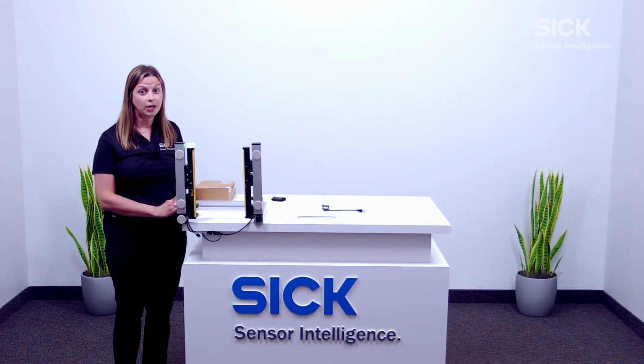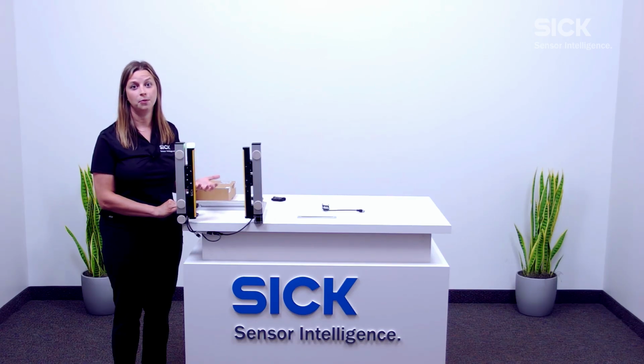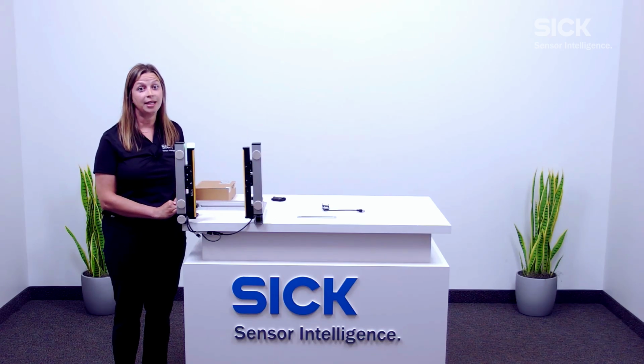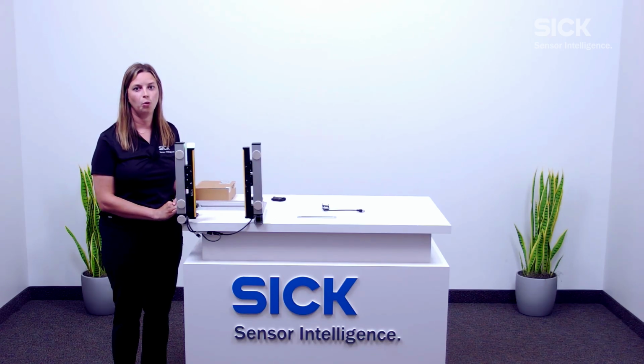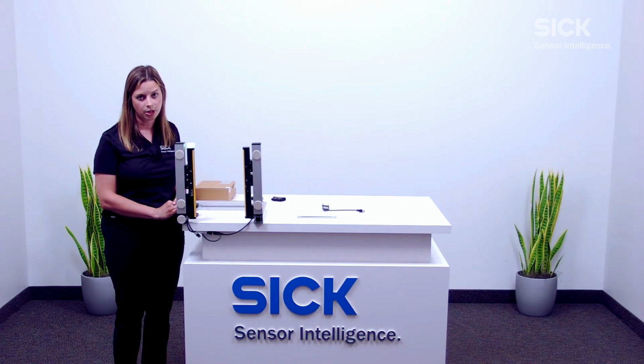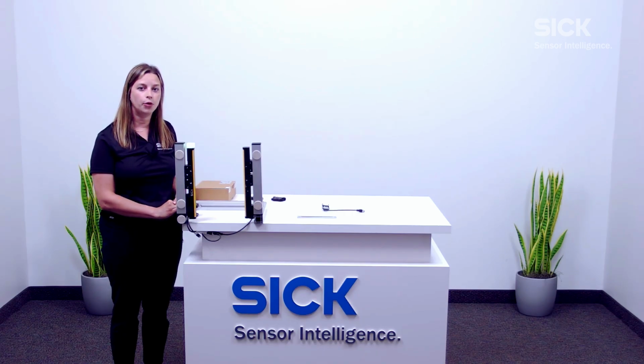At SICK, we actually have two different types of safety light curtains when we talk about resolution. The first one is 14mm resolution, which is used for finger protection. Then we have our 30mm resolution light curtain that is used for hand protection.